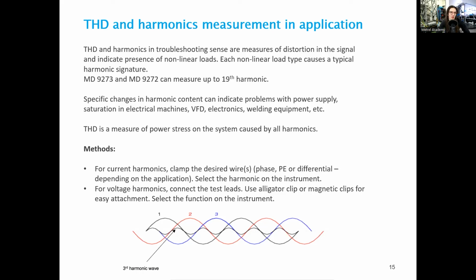Signals that contain a non-negligible amount of harmonic content usually indicate the presence of nonlinear loads in the system. While we have no ideally linear devices in reality, usually harmonics only need to be considered in systems where we have semiconductor solutions present, where we have magnetic devices that work in saturation or otherwise outside the linear part of the characteristic, where we have arc equipment, for example welding equipment, and similar nonlinear devices. The system needs to be designed to work with the expected harmonic content. So similarly to leakage currents, harmonics are also part of the design considerations for systems. But harmonics can be a very big problem, so where it is necessary, some filtering solutions are added to the installation to lower their presence.